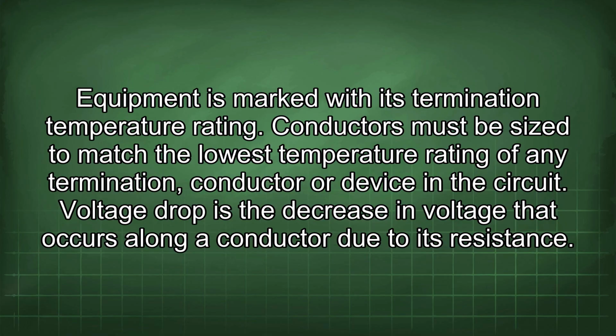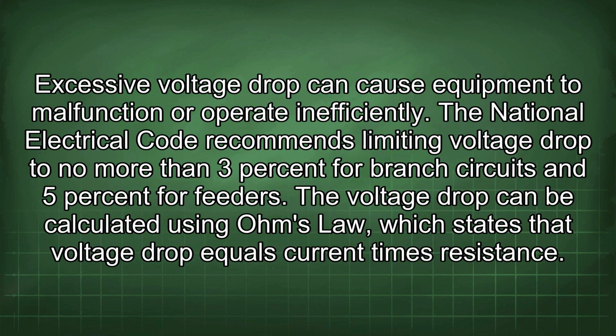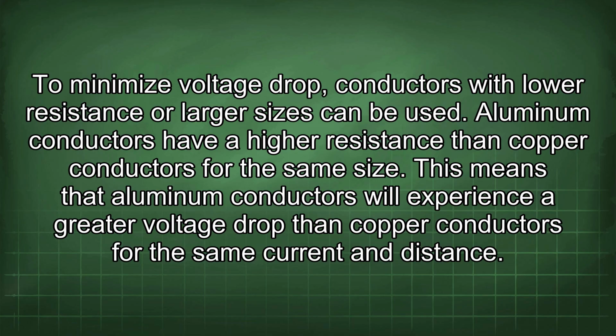Voltage drop is a decrease in voltage that occurs along a conductor due to its resistance. Excessive voltage drop can cause equipment to malfunction or operate inefficiently. The National Electrical Code recommends limiting voltage drop to no more than 3% for branch circuits and 5% for feeders. The voltage drop can be calculated using Ohm's law, which states that voltage drop equals current times resistance. To minimize voltage drop, conductors with lower resistance or larger sizes can be used.